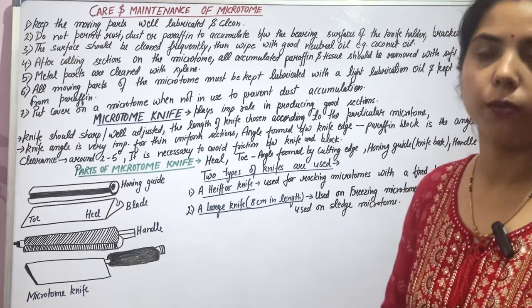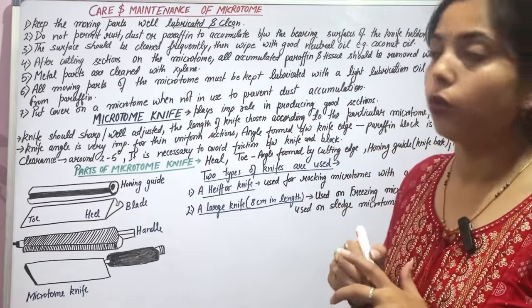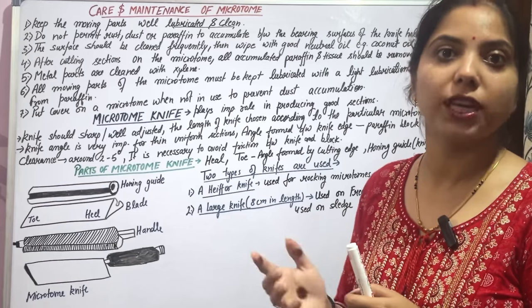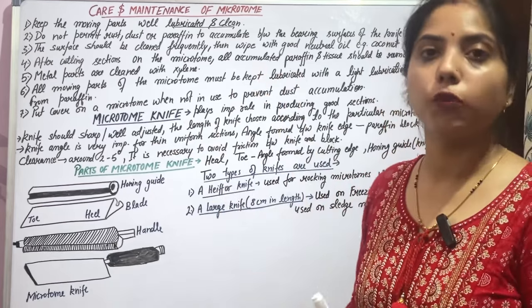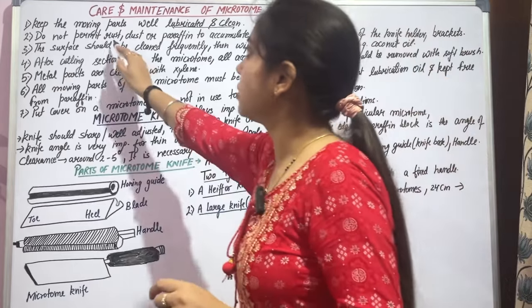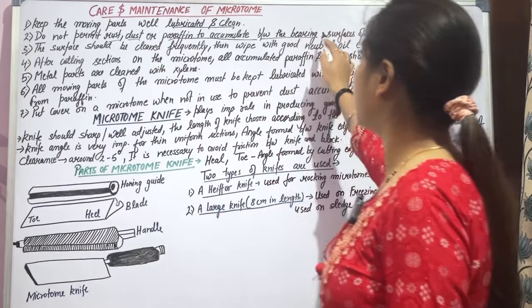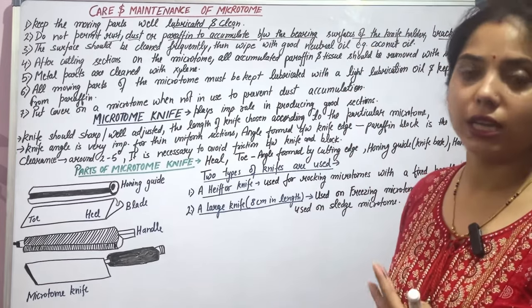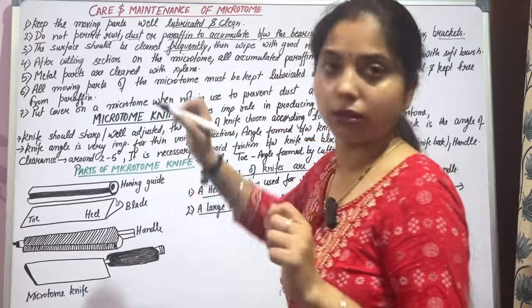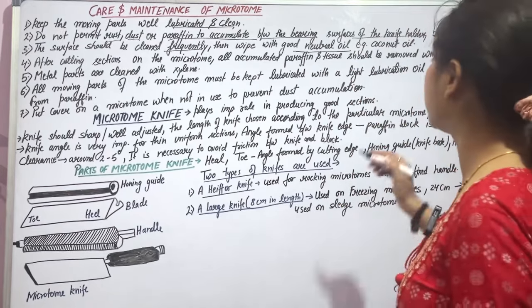Now let us look at the care and maintenance of the microtome. Keep all moving parts well lubricated and clean. Do not permit rust, dust, or paraffin to accumulate between the bearing surfaces of the knife holder and brackets. The surface should be cleaned frequently and wiped with a good neutral oil, such as coconut oil.